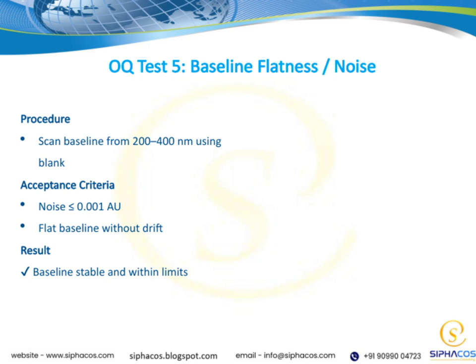Additionally, the baseline should be flat without any drift, meaning it stays steady without wandering up or down during the scan. The result we're aiming for is a stable baseline that remains within these limits. When we see a baseline that is flat and stable, it confirms that our instrument is performing well and that the measurements we take downstream will be reliable. Remember, maintaining a stable baseline is crucial for accurate and reproducible results, especially in sensitive analyses.